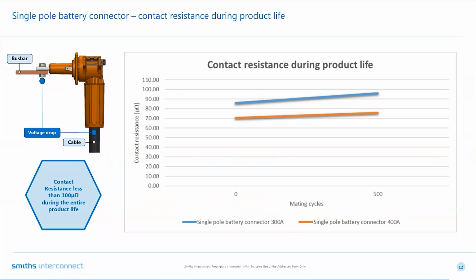The test is performed measuring the voltage drop between the bus bar receptacle termination and the crimp area on the plug termination. We perform the test at 0 mating cycle and after the entire product life of 500 mating cycles. The main result obtained is a stable behavior of the contact resistance value during all the product life, that is less than 100 microohm for the 300 amps size and less than 80 microohm for the 400 amps one. This limited performance drop in the connector life guarantees stable behaviors in terms of temperature increase during use, as contact resistance is the primary factor influencing connectors overheating.